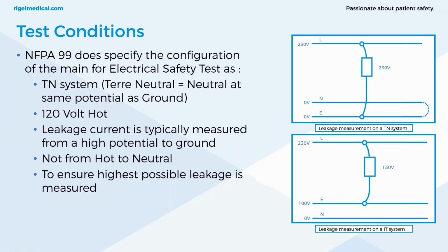Which is actually what's stated in NFPA 99 in one section, where an adapter can be used to temporarily produce an internal ground. You'll see that in section 10. So that eliminates this issue with the IT system. If you can get an adapter which will produce an internal ground, then you can perform electrical safety tests through that.